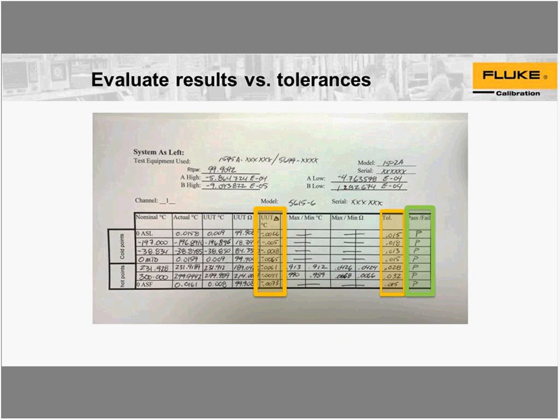Right. So looking at that data, we're taking the errors that we're seeing from the reference versus the UUT or DUT. We're comparing the tolerances that we have here. Now, your tolerances are generated from your uncertainty budget for your process. We go into that in this presentation, but it allows you to make a hard pass/fail determination whether your equipment is operating correctly or not.